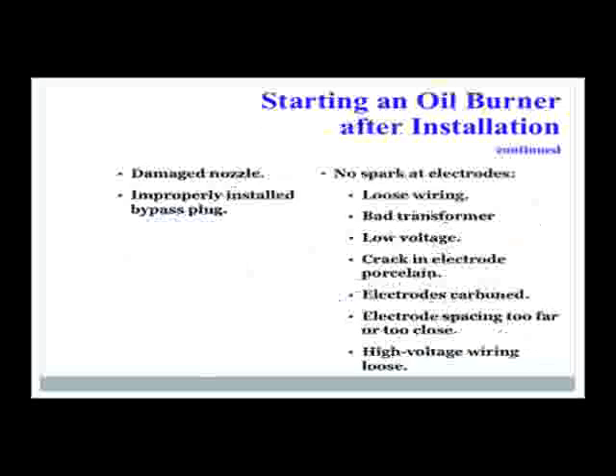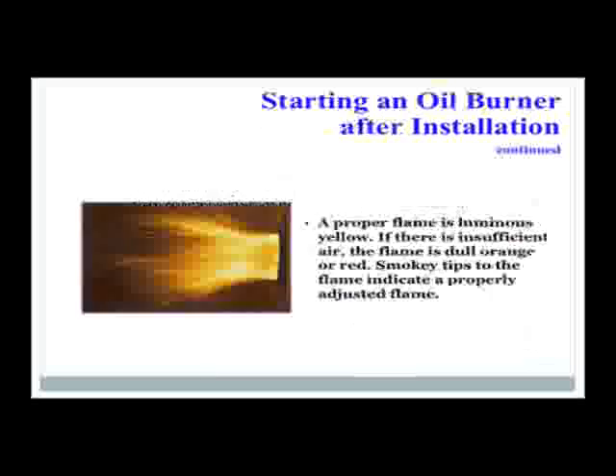No spark at electrodes. You might have loose wiring, bad transformer, low voltage, crack in electrode porcelain, electrodes carboned, electrode spacing too far apart or too close together. A proper flame is luminous yellow. If there's insufficient air, the flame is dull orange or red. Smoky tips to the flame indicate an improperly adjusted flame.